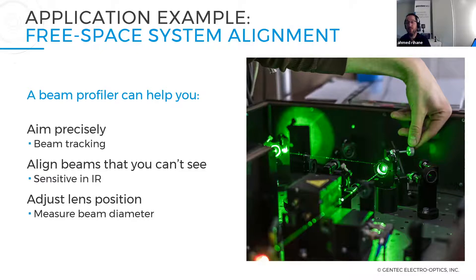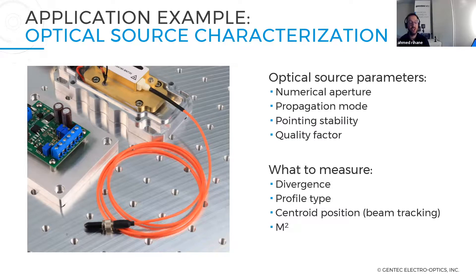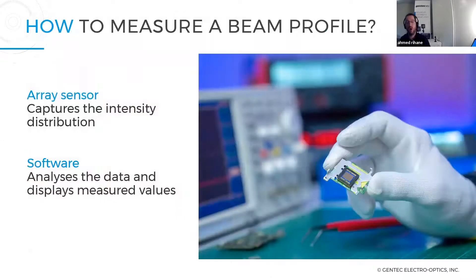A beam profiler is also very useful when working with wavelengths you cannot see, which is helpful for adjusting and aligning your beam. Another application is optical source characterization, where you need to know the numerical aperture, divergence, mode — multi-mode or single-mode — and pointing stability. You can do that by measuring divergence, profile type, and center position.